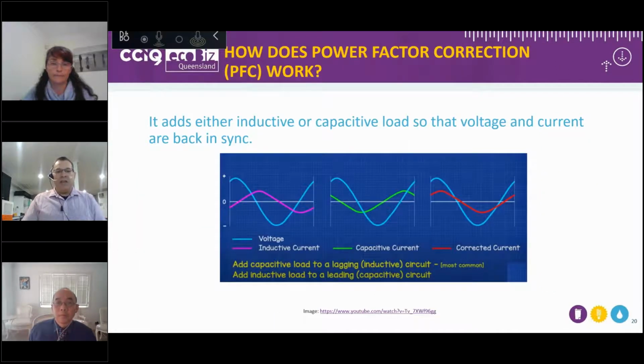Whether power factor is leading or lagging, there is a very specific way that it can be corrected, and that's through the use of power factor correction equipment. What power factor correction equipment does is simply bring those waves back into alignment, so the power factor can return to 1, or as close to 1 as possible, for that particular site.